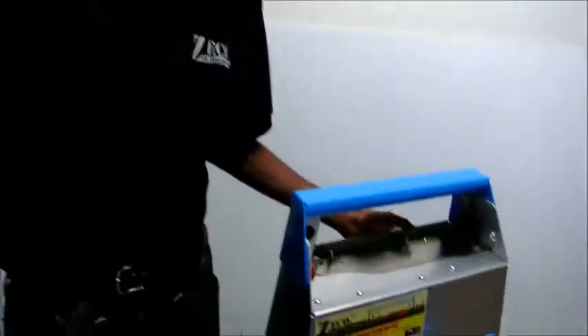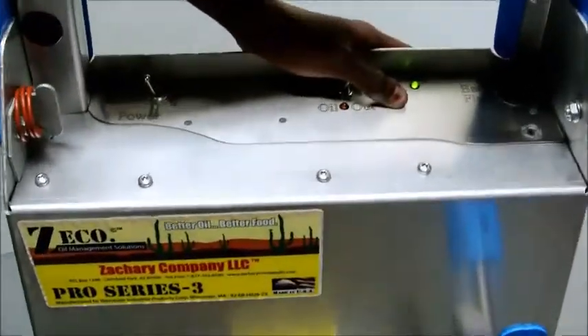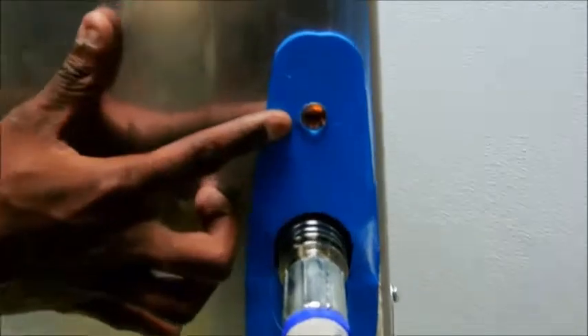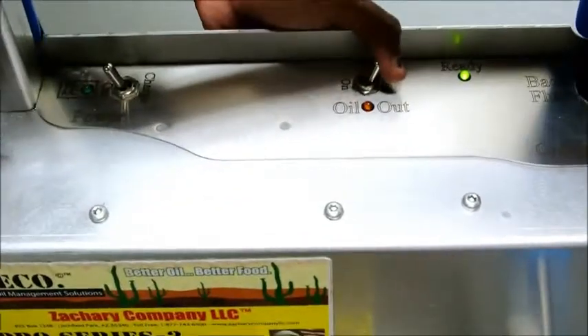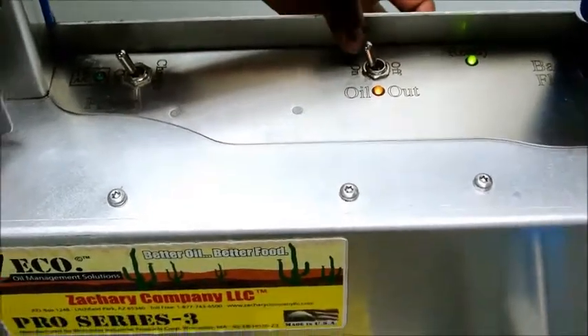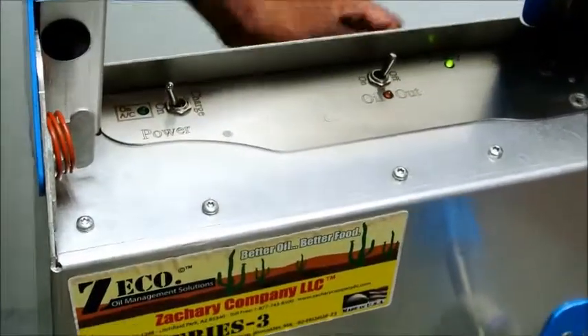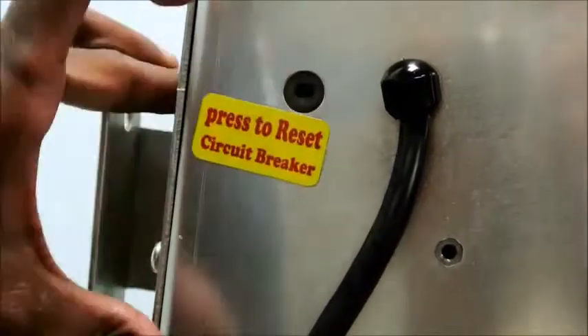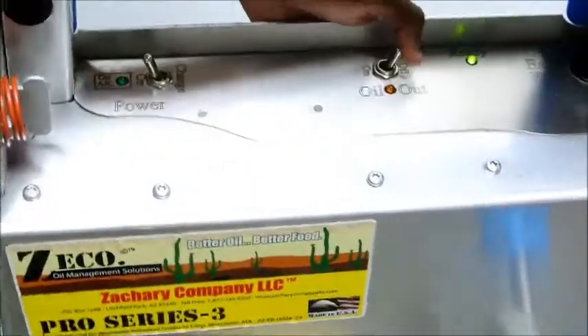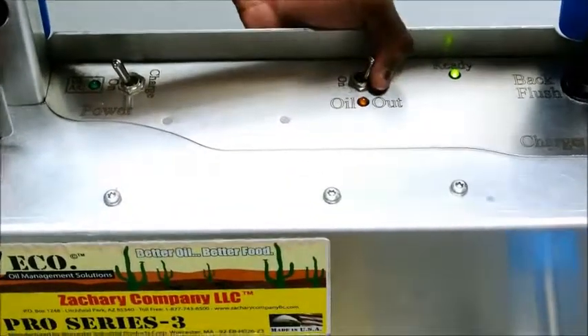If you have your ready LED light on, as well as your safety LED light on, and you come up to your oil out switch and turn it on, and you still don't have power, turn your oil out switch off, come over to the side, and hit the reset on the circuit breaker, then come back up to the oil out switch and turn it to on.